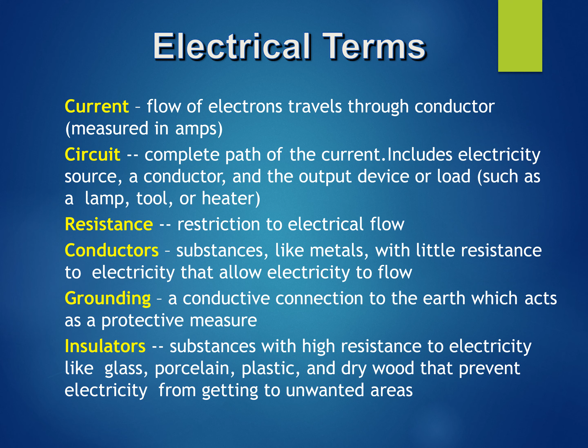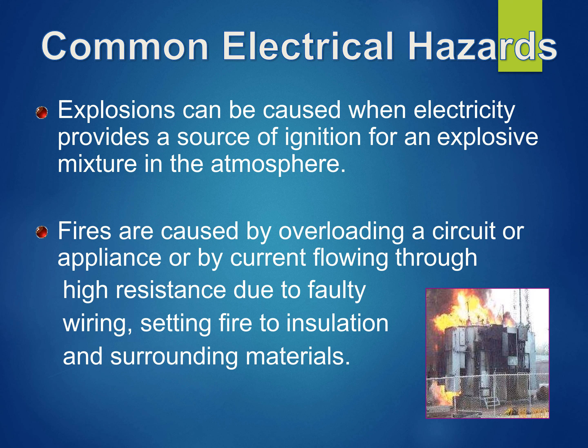Here is an example of the cause of overloading. For example, you have a washing machine in your house, and the connecting wire's cross section is too small, for example number 14 American wire gauge. When the machine starts drawing power from the supply, the wire will eventually overheat, and with prolonged usage fed from a small wire, it will eventually lead to fire.